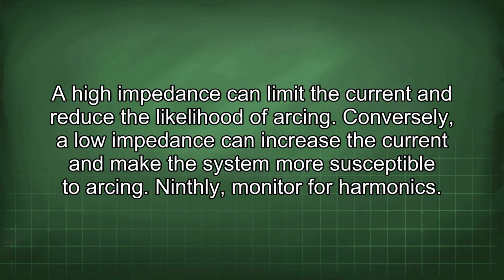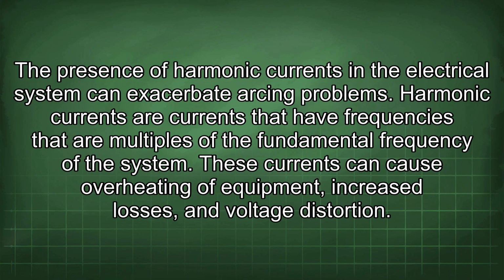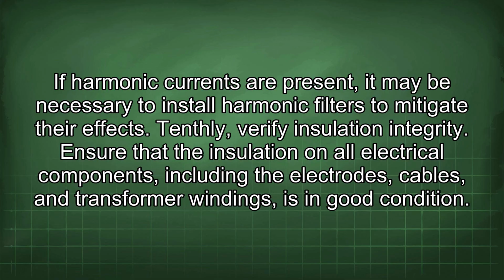Ninthly, monitor for harmonics. The presence of harmonic currents in the electrical system can exacerbate arcing problems. Harmonic currents are currents that have frequencies that are multiples of the fundamental frequency of the system. These currents can cause overheating of equipment, increased losses, and voltage distortion. If harmonic currents are present, it may be necessary to install harmonic filters to mitigate their effects.